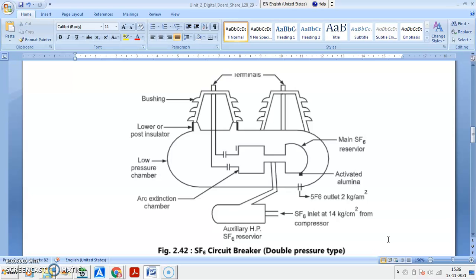Then you are having, this is a low pressure chamber over here. So you are having gas system, you are having tank, and you are having arc extinction tank, inlet gas system, arc extinction, SF6 main reservoir, and this incoming terminal and outgoing terminal. So, terminals opening and closing. This is the arc extinction chamber, inside which arc extinction takes place. Gas system is followed with closed path.